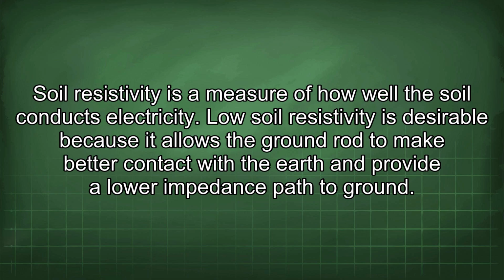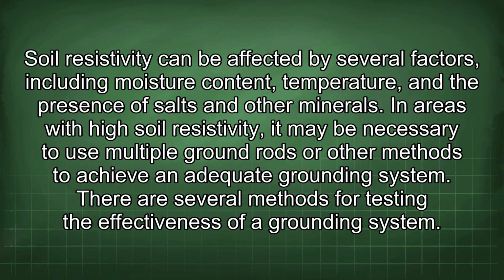Soil resistivity is a measure of how well the soil conducts electricity. Low soil resistivity is desirable because it allows the ground rod to make better contact with the earth and provide a lower impedance path to ground. Soil resistivity can be affected by several factors, including moisture content, temperature, and the presence of salts and other minerals.